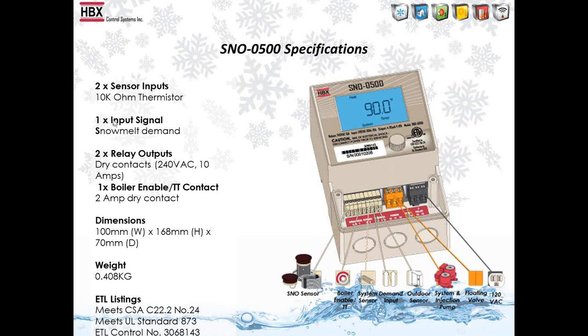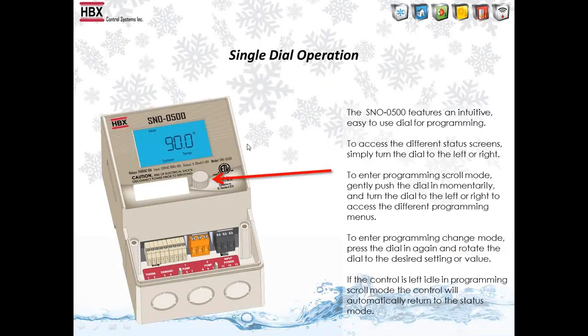So 2 sensor inputs, so 10K sensors. So you have a system sensor, you have an outdoor sensor, we have a boiler output, we have the actual snow melt sensor, our pumping outputs, and then 120 VAC in, obviously. Like I said before, single dial operation, so it is fairly intuitive to use. The one downfall about the SNO-0500 over the SNO-1000 is that it does only show one parameter on the screen at a time. So when you go through the parameters, you will only see one at a time, which compared to our 1000 series controls is a little bit of a downfall, but this control is far less expensive than the 1000, so we do sell a lot of them because of that.